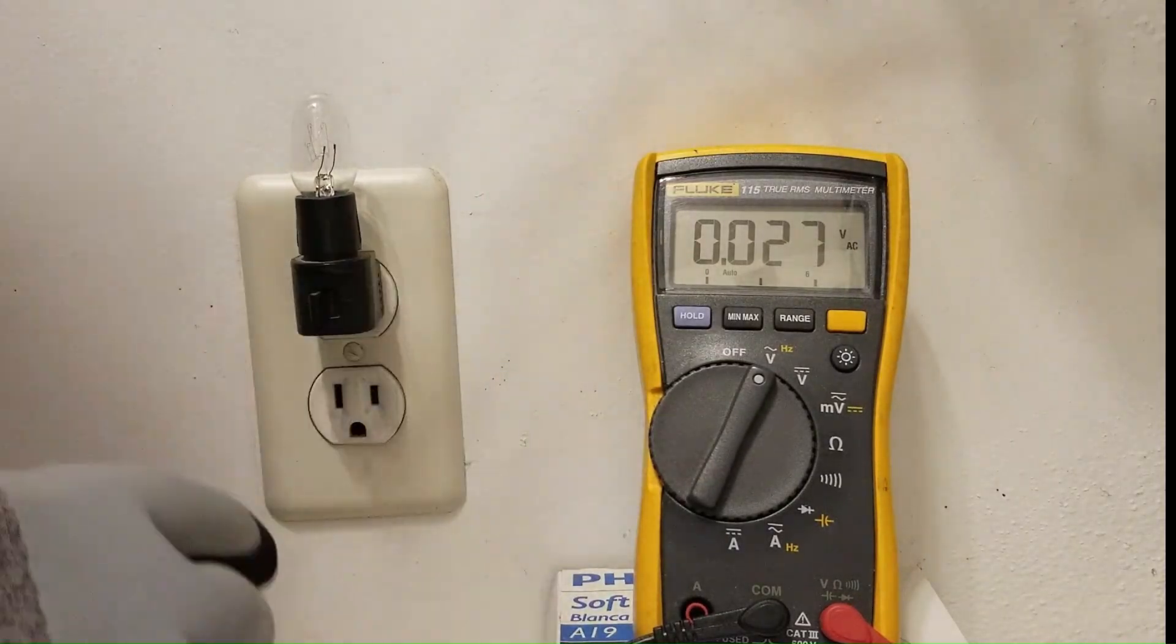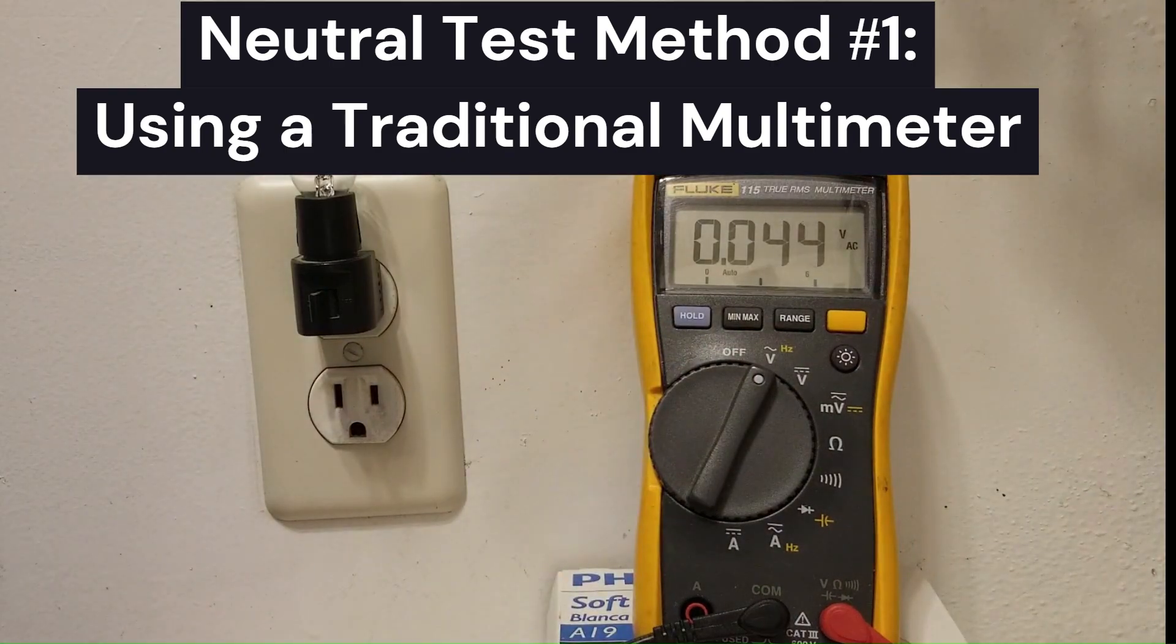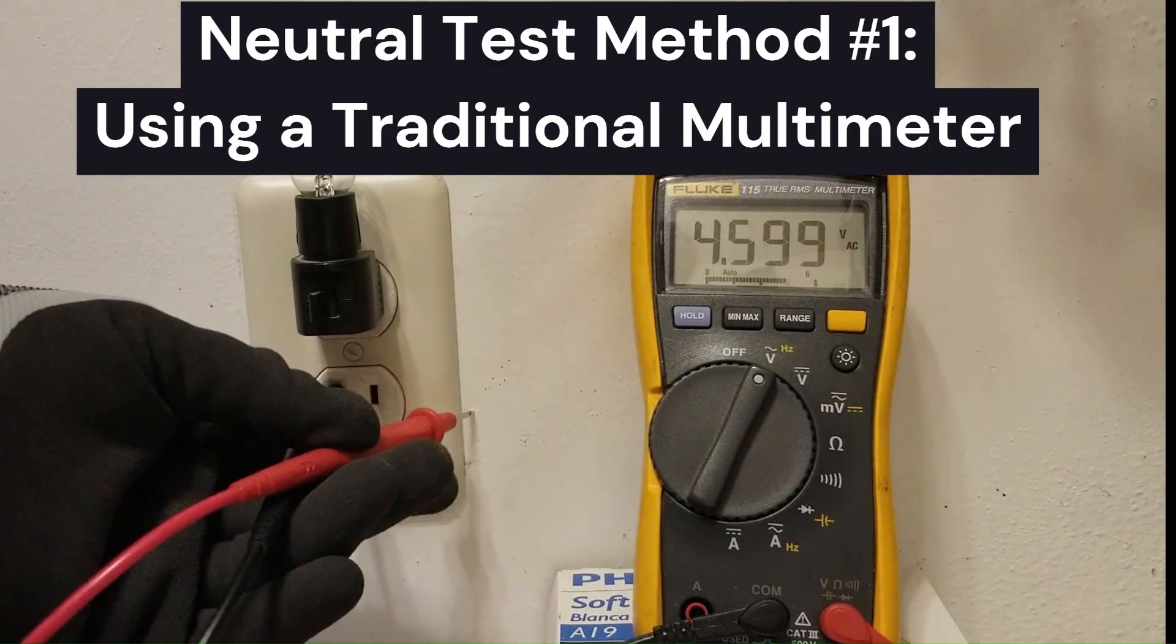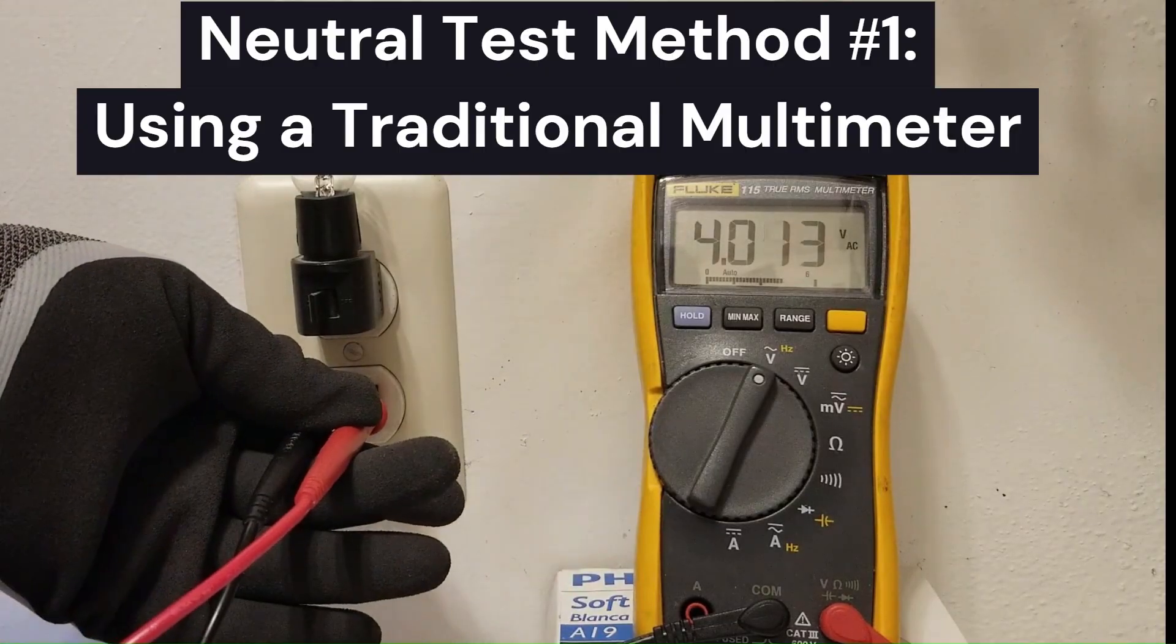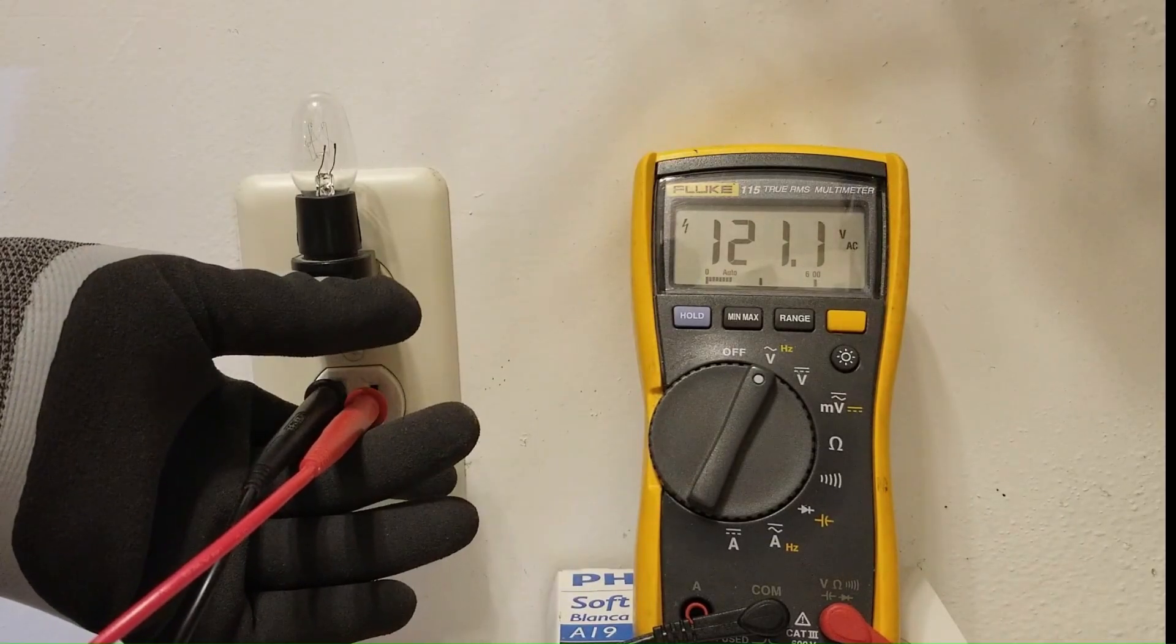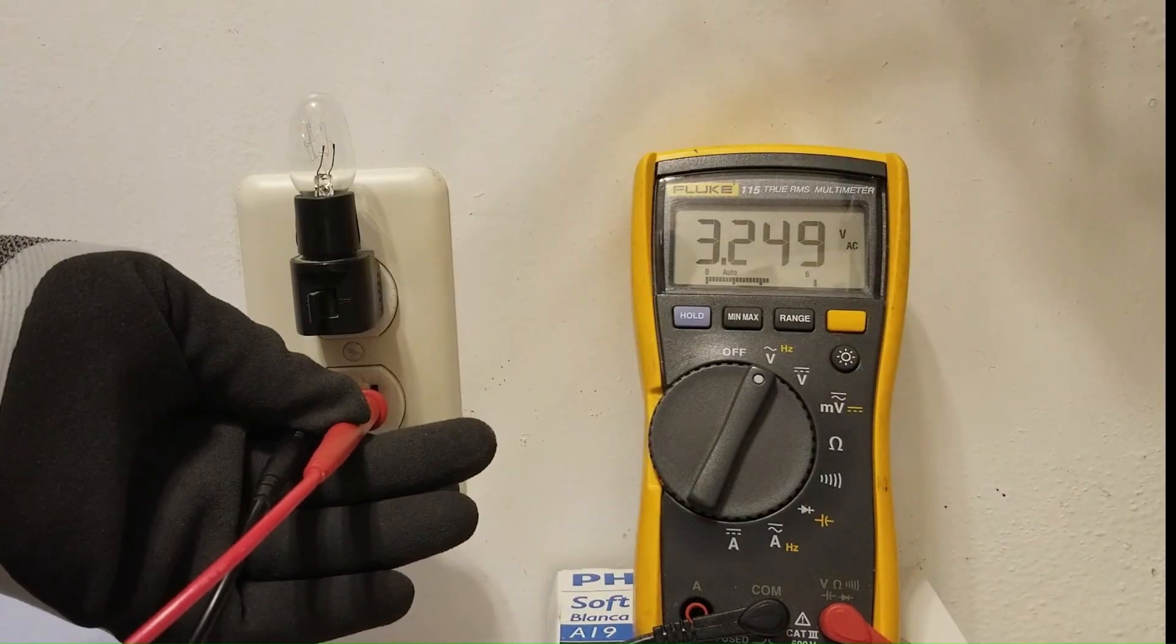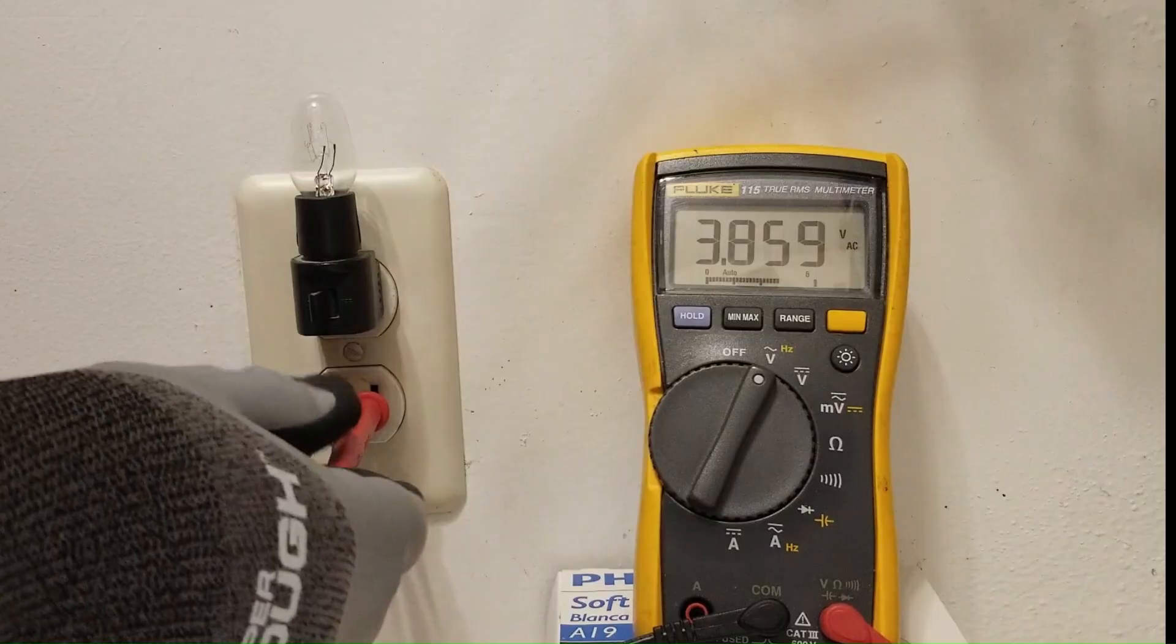So I want to show you how you can test for a bad neutral by having a load in the socket. And as you noticed, the voltage dropped down to around four volts when I turned this light on. I turned the light off, it goes back up to 121 volts. I turn it back on and it drops down to just around four volts.